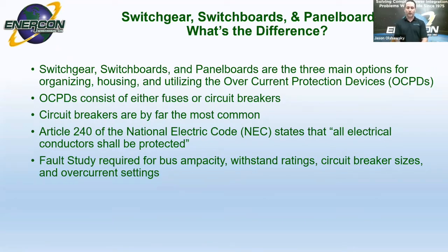NEC Article 240 states that all electrical conductors shall be protected. So overcurrent or short circuit faults, if not interrupted, can lead to damage to equipment and even fires in that facility. So fault studies are also required for equipment withstand ratings, or fault current, circuit breaker sizing, and overcurrent set points. And we'll get into some more of these items in more detail in the next few slides.